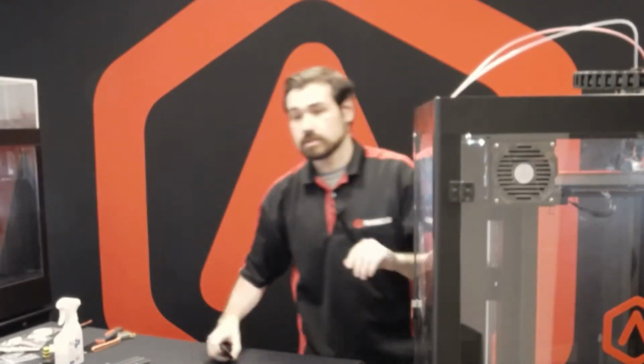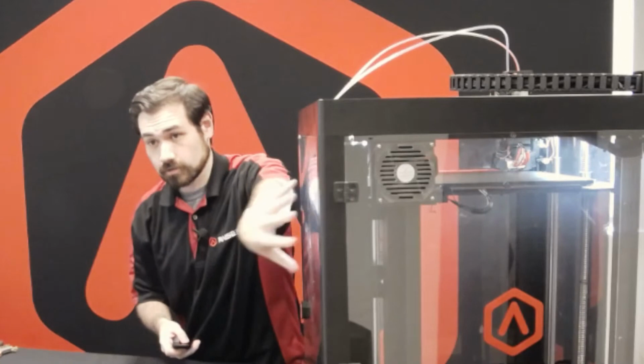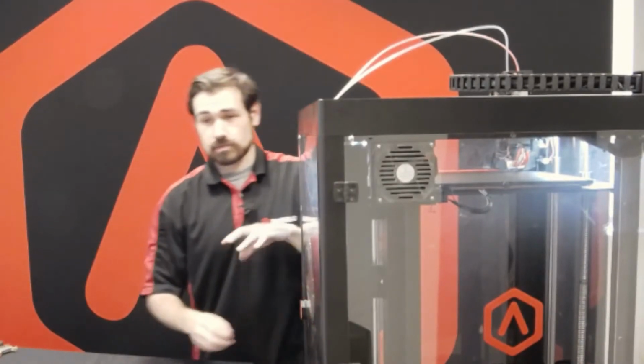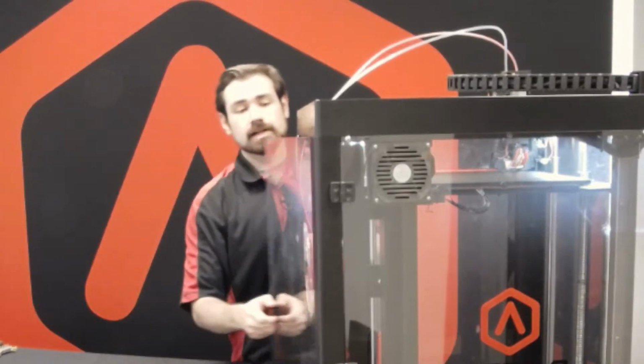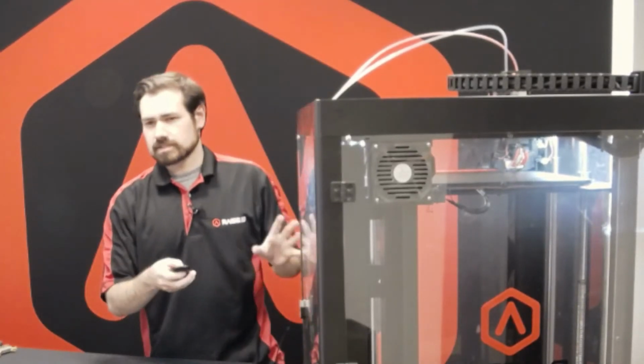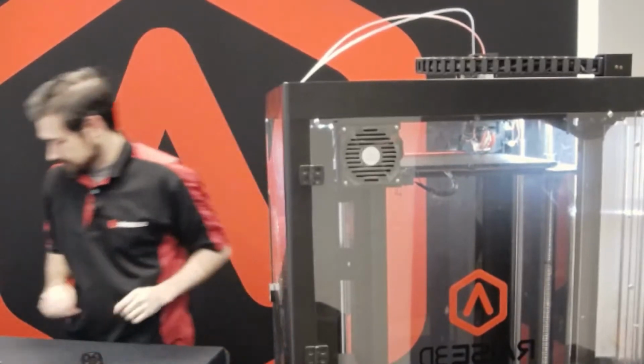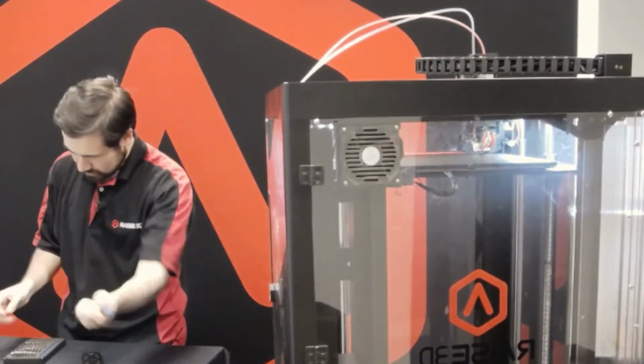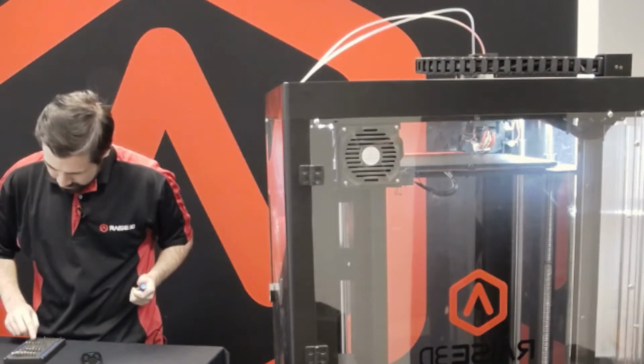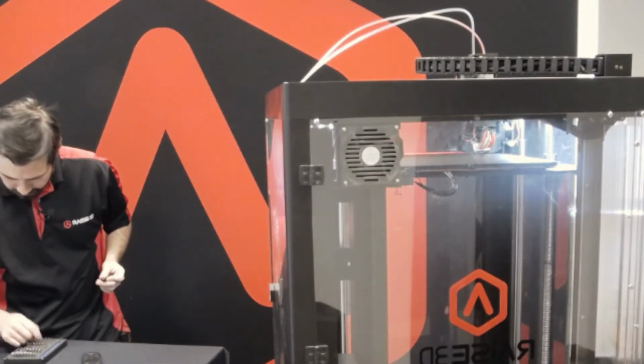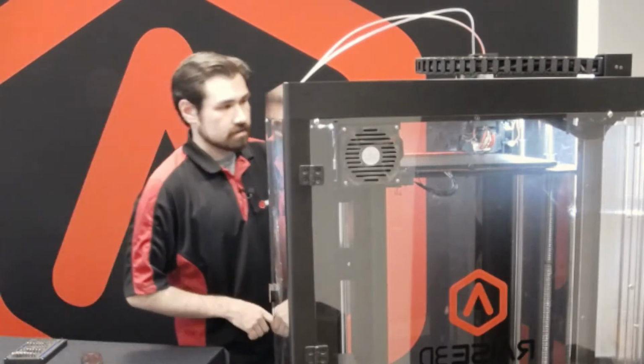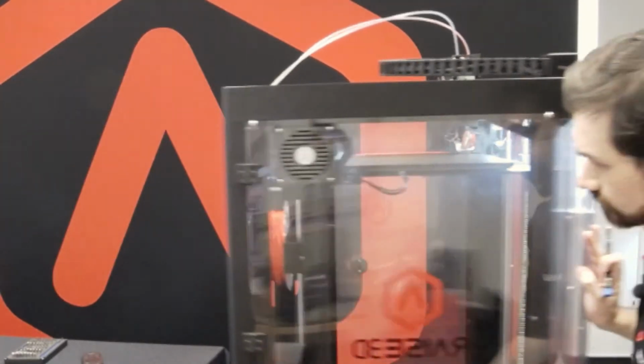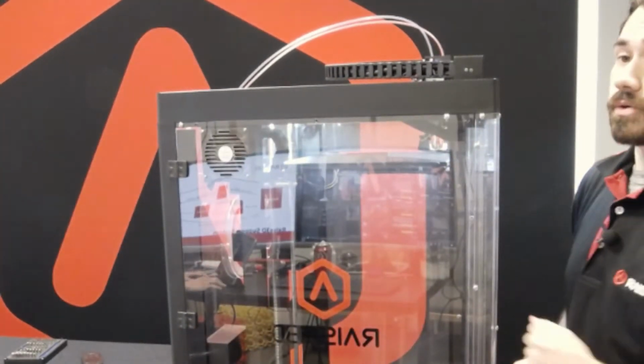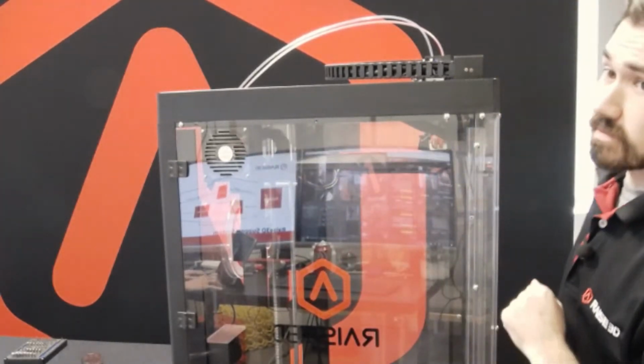So to get to that back filter, we will need to uninstall the back panel, which is connected to the filament side door. So that is one thing to keep in mind. It can be kind of bulky, but it's not too difficult to get this off of that upper section. It is a Phillips head screwdriver, so I'll be working with one of those. And then this back HEPA filter fan is always on while the machine is running. So in order to just run this replacement, I'll go ahead and make sure my machine is off.